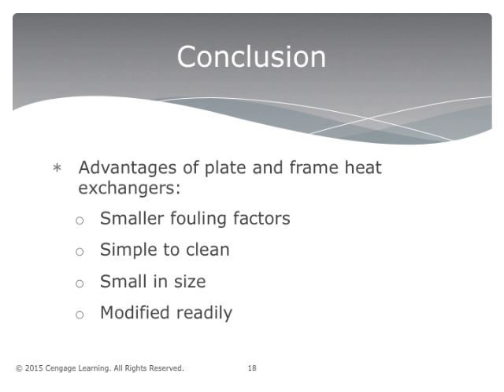To review, the main advantages of plate and frame heat exchangers over other heat exchangers include the following. They have smaller fouling factors due to the reasons discussed previously. They are simple to clean, and chemical cleaning methods are rapid and highly effective. Mechanical cleaning is easily performed because they can readily be taken apart. They are small in size and can be modified readily. If an existing exchanger cannot transfer the required amount of heat, for example, one or more plates can easily be added as needed.